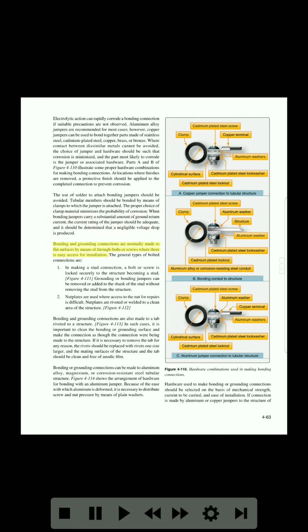Bonding and grounding connections are normally made to flat surfaces by means of through bolts or screws where there is easy access for installation. The general types of bolted connections are: 1. In making a stud connection, a bolt or screw is locked securely to the structure, becoming a stud. Figure 4-111. Grounding or bonding jumpers can be removed or added to the shank of the stud without removing the stud from the structure. 2. Nut plates are used where access to the nut for repairs is difficult. Nut plates are riveted or welded to a clean area of the structure.